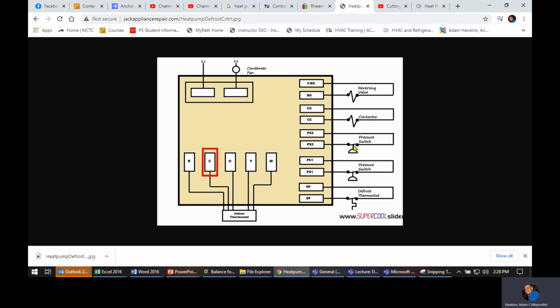If one of those switches, or it's on a high pressure and the condenser fan's out, and so it has kicked itself out, that can keep, in cooling or in heating, that can keep the contactor from pulling, which can look like you've got another issue, but it's really something to do with the pressure. So the way you check your board is you're going to see if you've got power coming in and if you've got power going out.